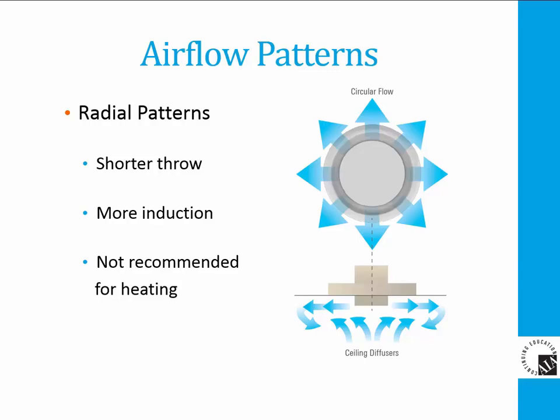Circular flow patterns have high induction of the room air into the discharge jet and have a tendency to have the air curl back at the end of the jet toward the diffuser. Radial air patterns are well suited for variable volume VAV applications and cooling only applications, but are not well suited for heating applications.